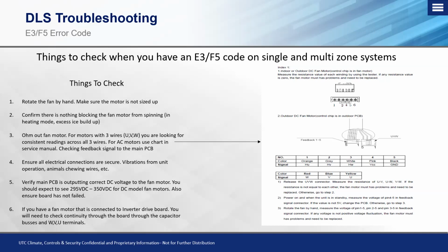So you can confirm, hey, I actually do have a motor issue, and it is because of this signal feedback. Okay. Now, if you do have a positive voltage fluctuation, then that fan motor is perfectly fine. It's sending a correct feedback signal, and if you're still getting those error codes, you might want to start investigating into that main PCB board that this 5-wire Molex plug is going to be connected to, because there could be an issue with that board receiving the feedback from the fan motor, and it's coding out and giving you a false positive. Okay, and again, those are just some things that we can do to check those motors.